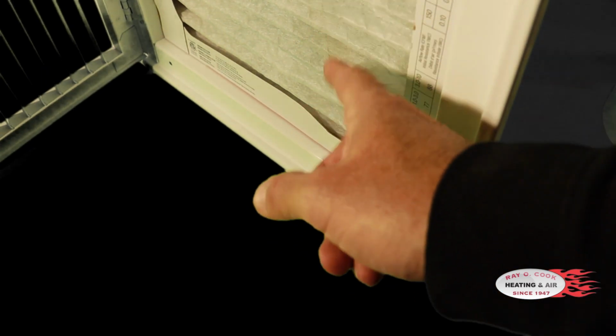Well, that duct is in the attic, and that duct is probably not sealed airtight. So if you increase the restriction and the resistance here with a filter, you're going to cause whatever ductwork is between this and your unit to suck more air through leaks out of the attic. And that's on the other side of the filter. That dirt and debris is not going to be caught in the filter. It's past it. And that's where you can make your air quality even worse by investing in too restrictive of a filter here and sucking undesirable air out of your attic.